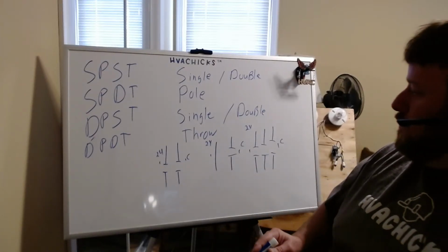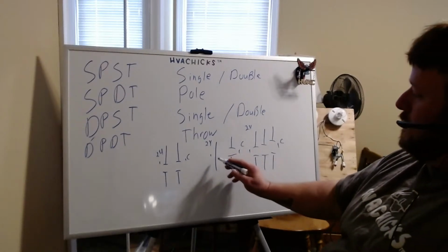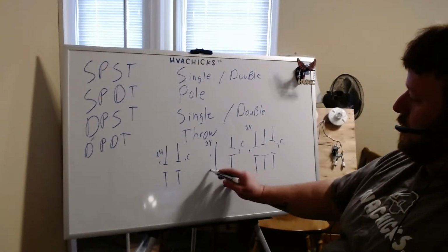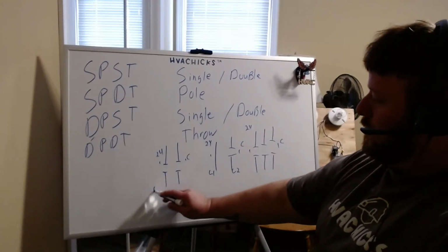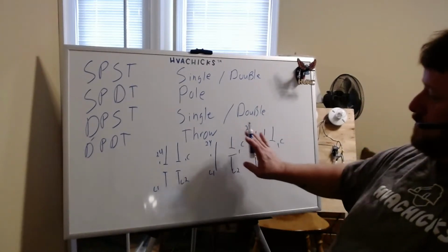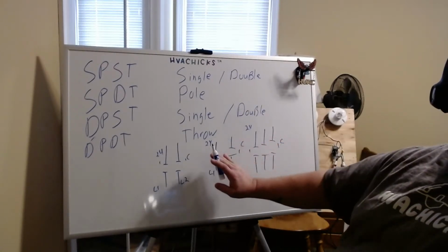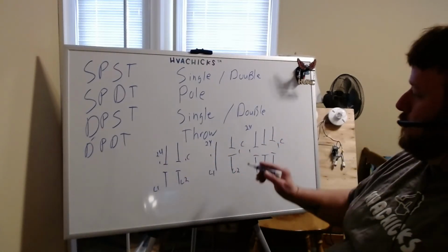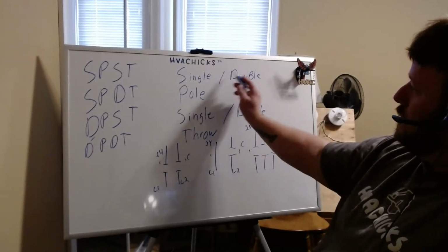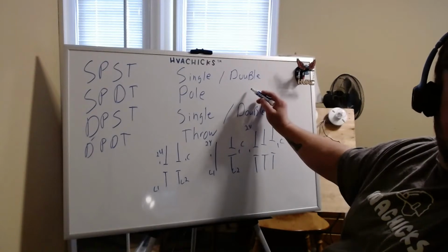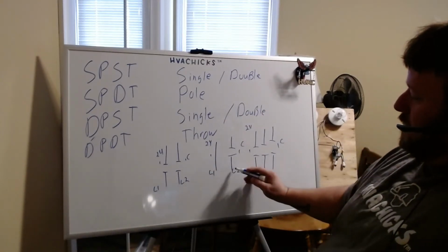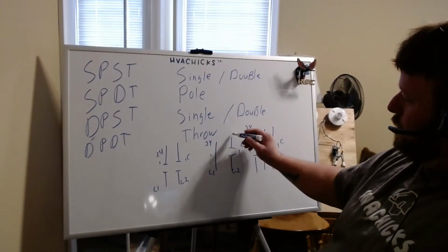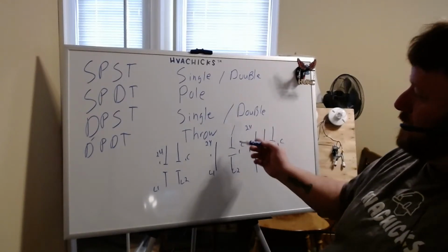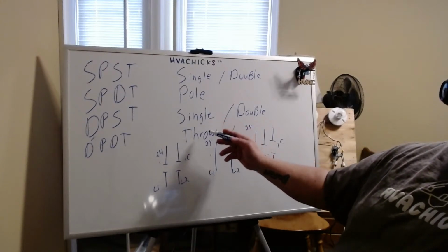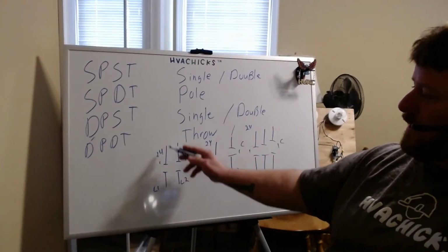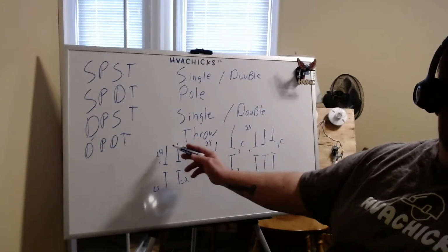And if you're kind of figuring out where we're going with this, contactors. So L1, L2, L1, L2. This is what everyone sees in the field for us. Single pole, double pole. So we're focusing on this top part here, single pole and double pole. Now this is a single pole, and it's got one point of contact, so it would say single throw. Double pole, 2 points of contact, double throw. We're energizing 2 points, energizing 1 point.